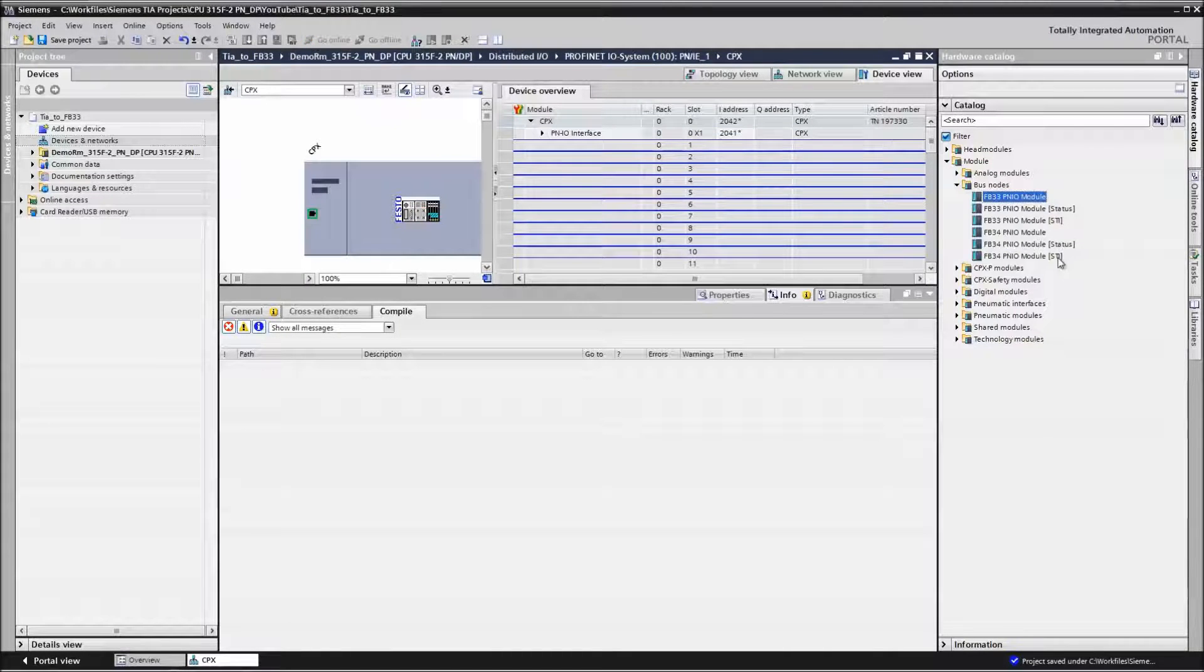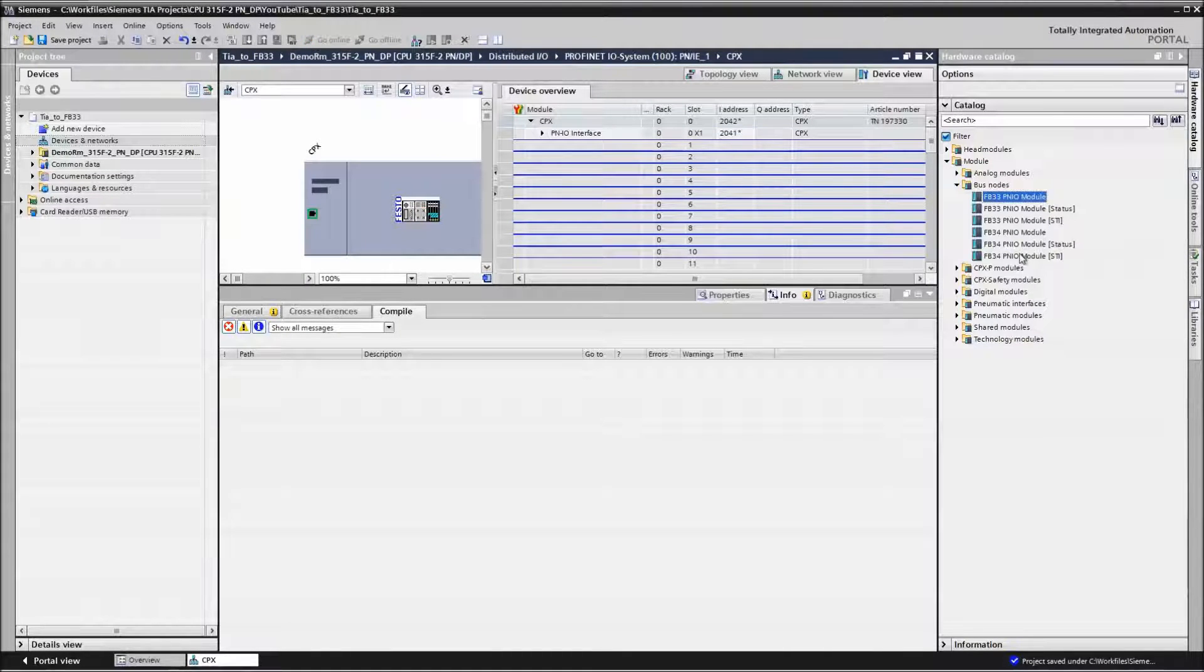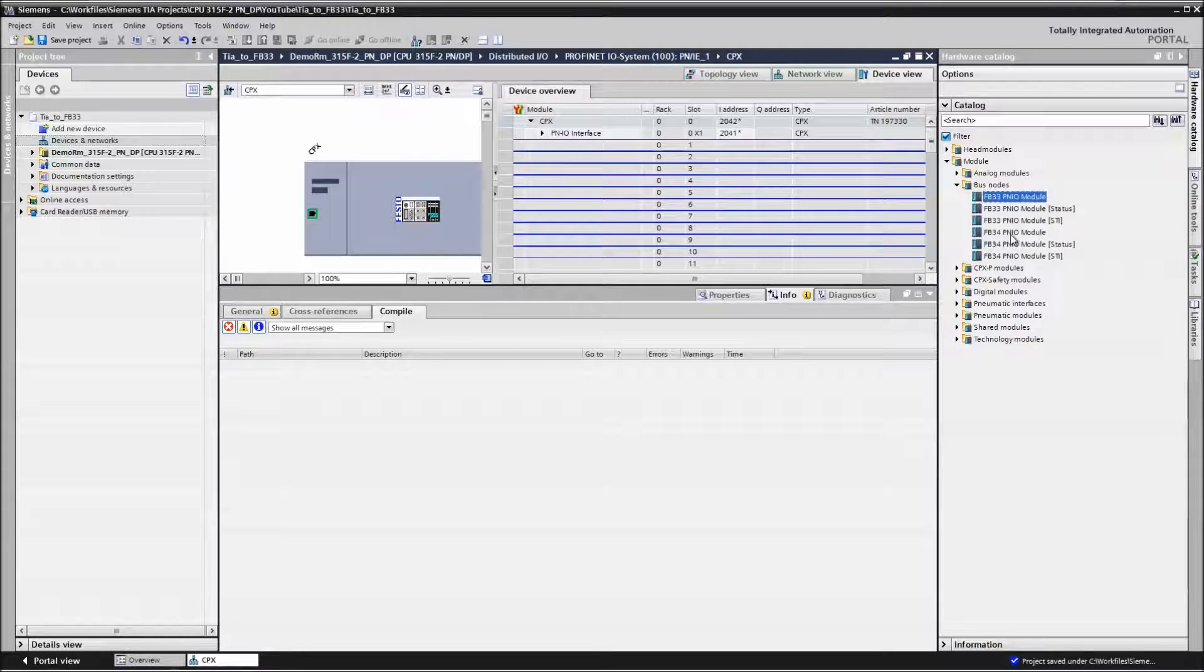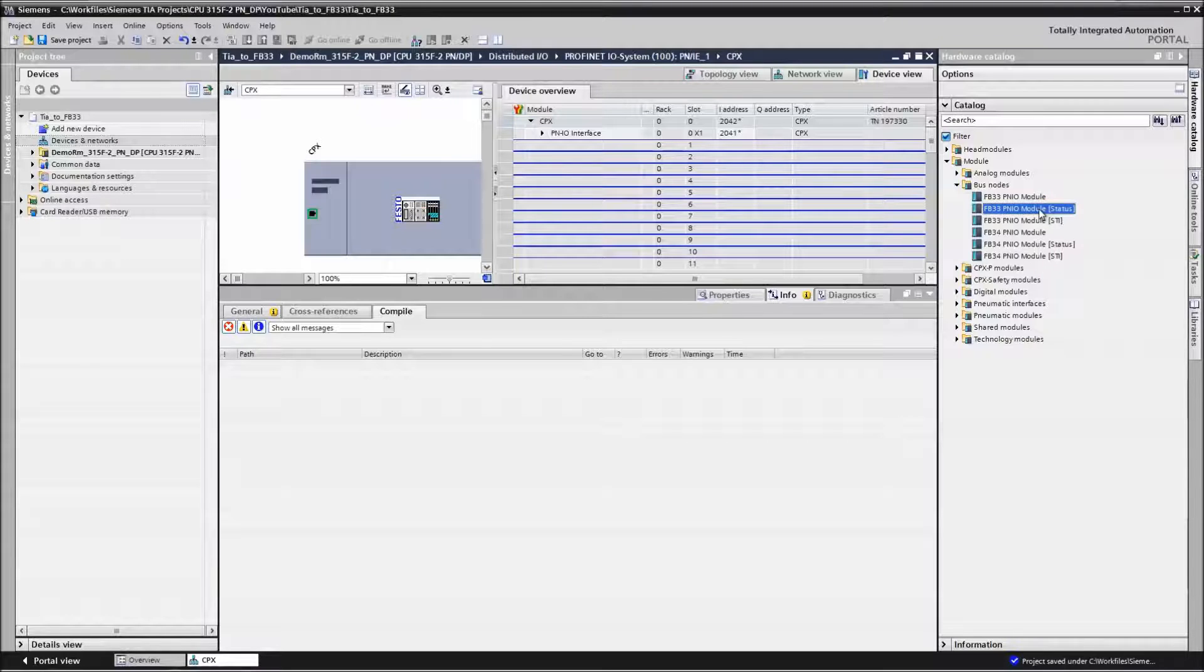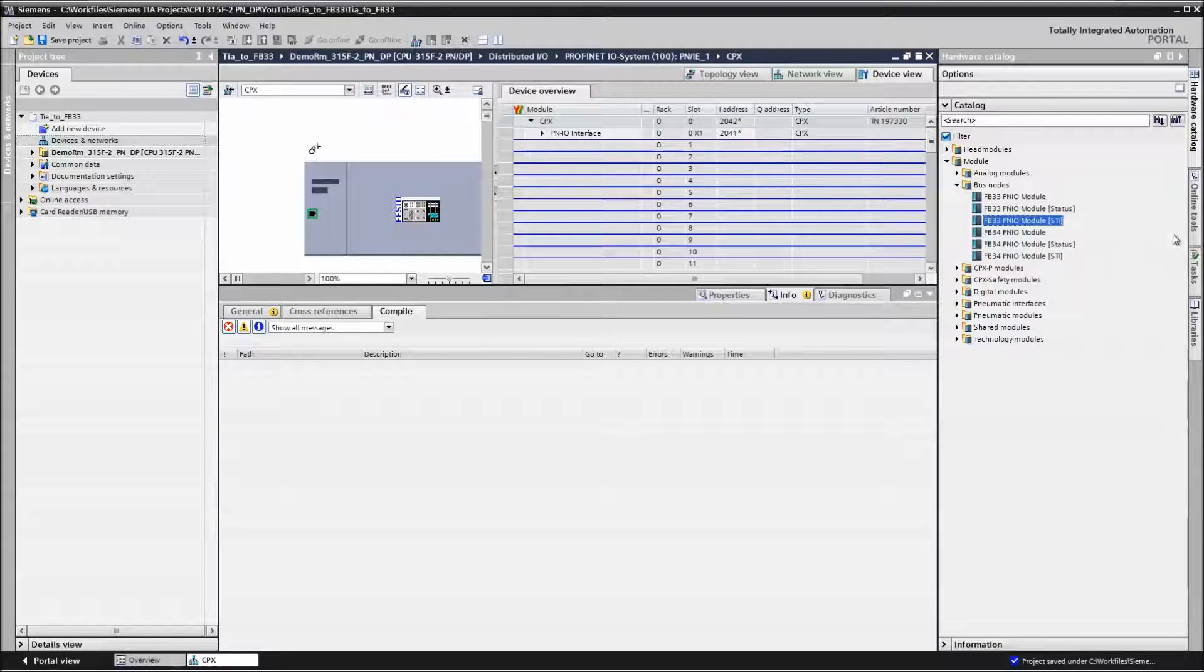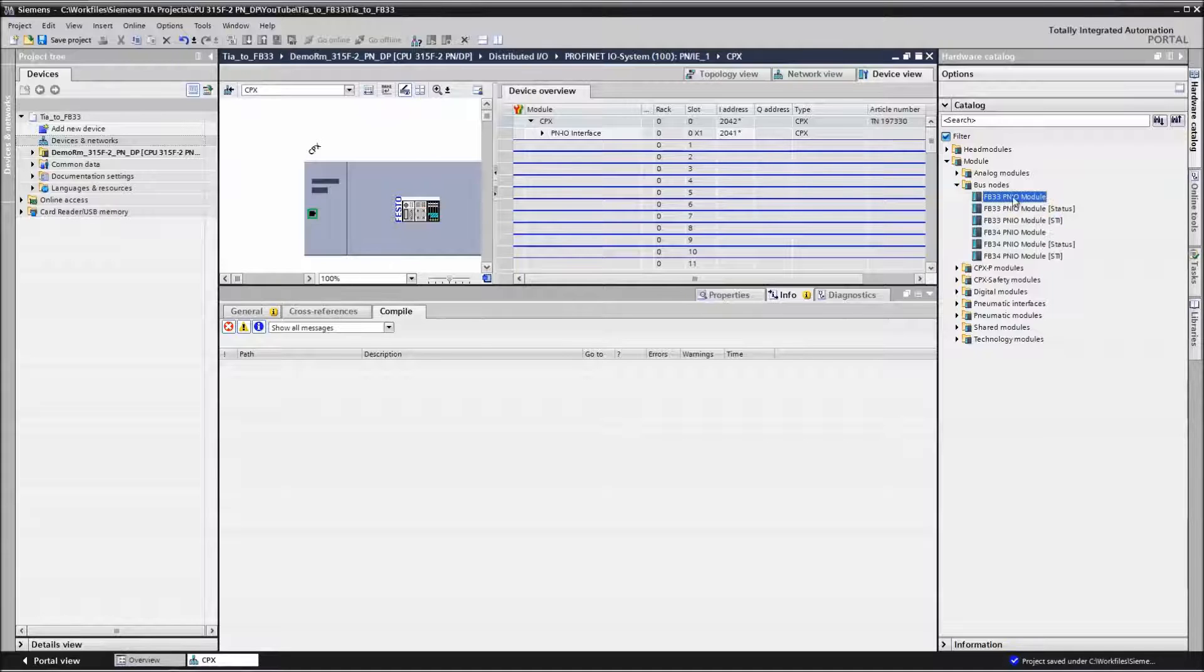And now we're going to add modules to the CPX manifold. And this over here is important because based on the DIP switches that you have on your module, that decides what you actually choose. I have no status and no SDI selected. So I just have a basic module here. So I'm going to drag that in over here.